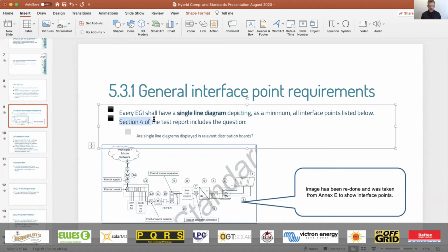And then, of course, in section 4 of the test report. So in your solar PV test report, when you issue a certificate of compliance on your installation, one of the questions it needs to satisfy is, are single line diagrams displayed in the relevant distribution board? So the standard is going to make it compulsory for you to have a single line diagram of your solar installation fitted inside the DB board. I think this is a great addition.